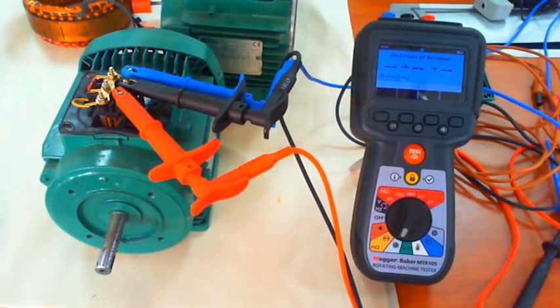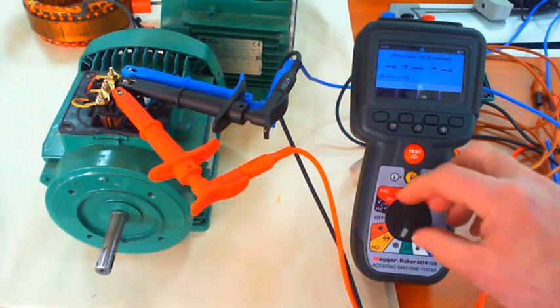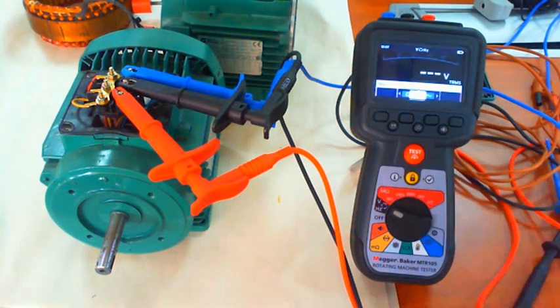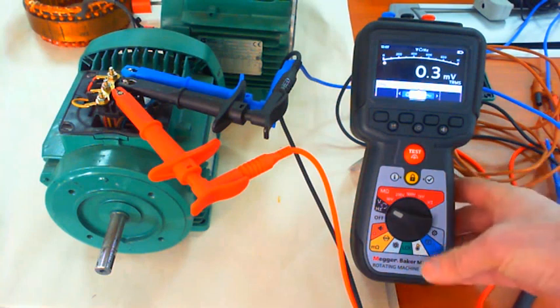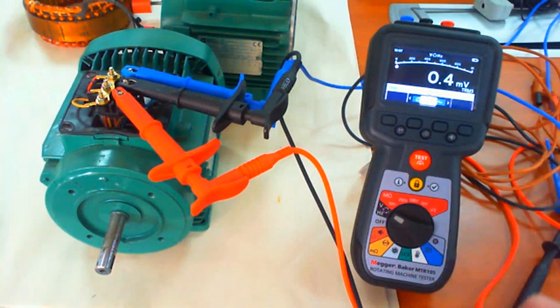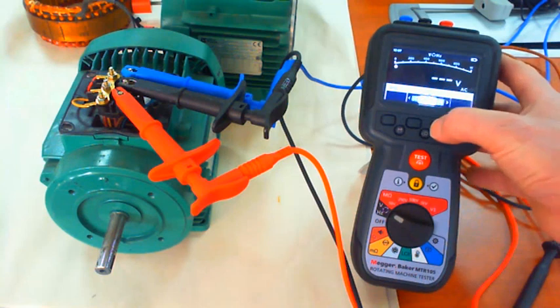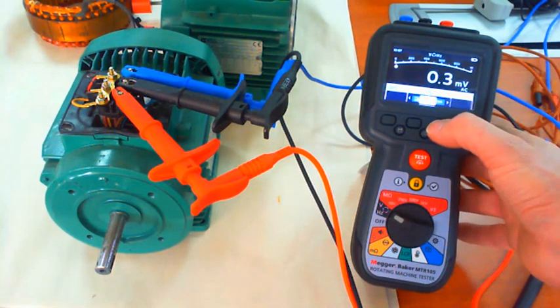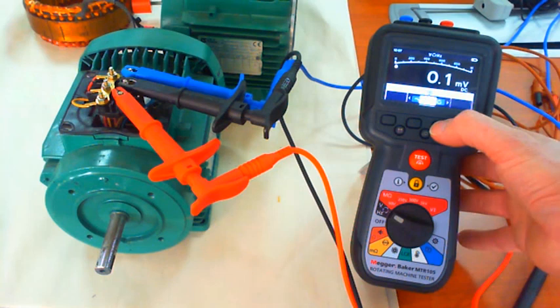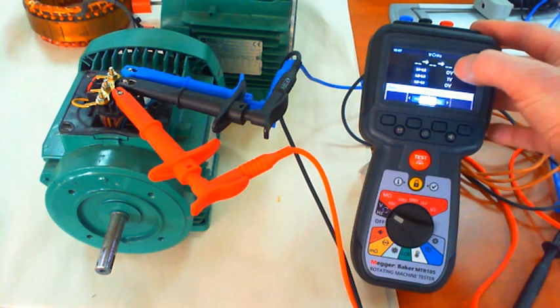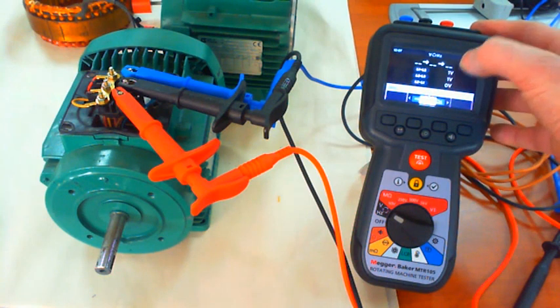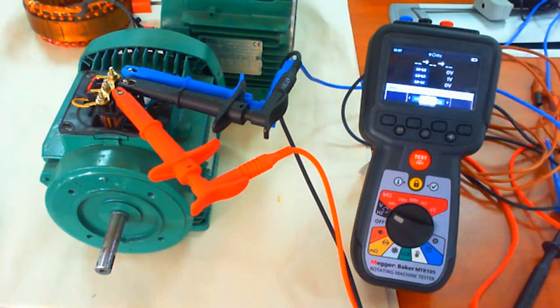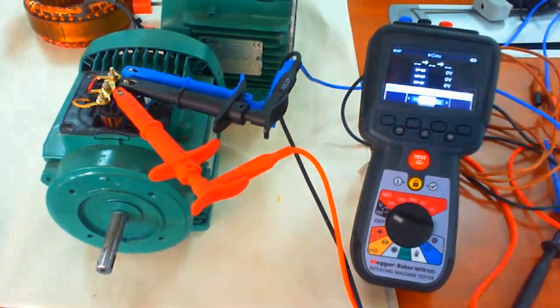I can't demonstrate the power supply direction rotation, but I can obviously show you the screen. So this is our voltmeter. We have our soft keys here, so I can scroll through the tests. We've got AC measurement, we've got DC measurement, we've got supply phase rotation. So this is where it would measure phase to phase, L1 to 2, 2 to 3, 3 to 1. And it would then give us the direction of rotation. It will give us the frequency, and the direction of rotation would be L123 or L321.